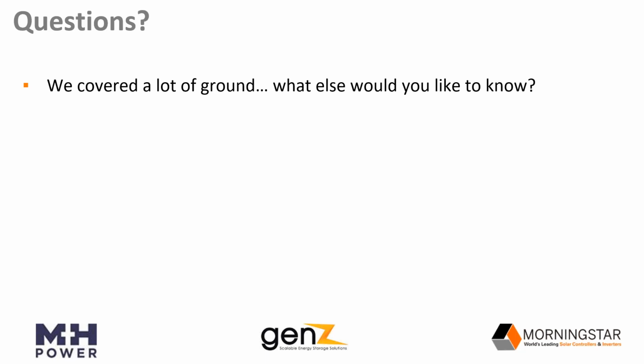Okay, so a question here coming from Gerard. Do the genZ battery modules have a communication bus, in other words, CAN, etc., that can be monitored to see the state of each module? Yeah, no, we don't. In fact, we intentionally eliminate that. Typically when you commission a genZ battery, we always recommend, and it's in our installation manual, to bring the battery up as a whole, as a bank, so that all batteries are balanced, and that would avoid imbalances in the long run. So yeah, no, we don't have CAN bus communication. Okay, well, thanks for that answer.